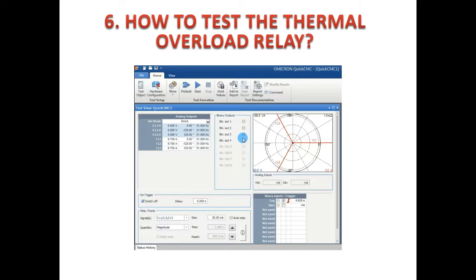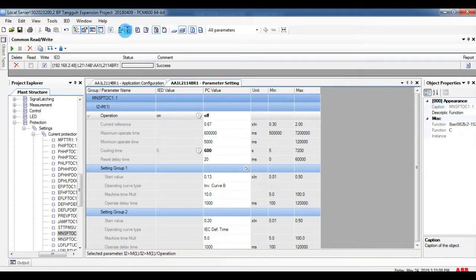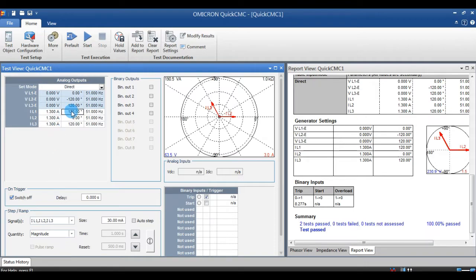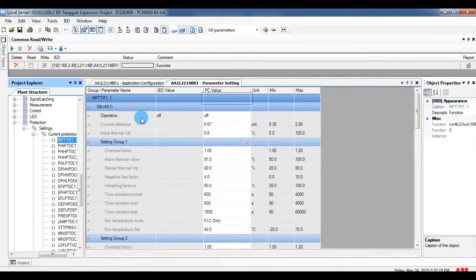Next, how to test the thermal overload. I am going to show this using the REM620 motor protection relay and the Omicron test kit. Before testing the thermal, I should disable all other protections. To have a clear understanding: when you go for testing, this may overlap with other protections, so in order to avoid that, we can turn off all other protections and enable the thermal overload protection alone.